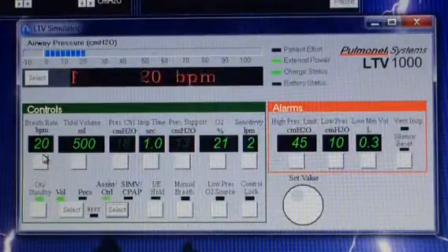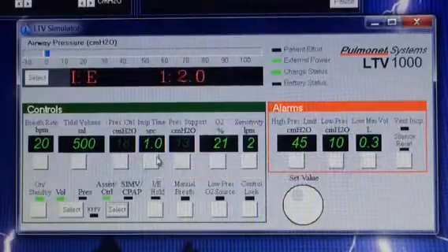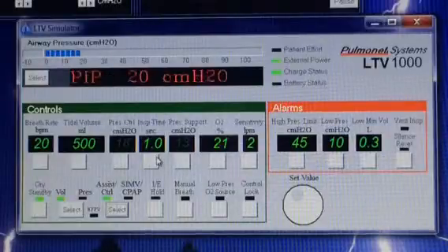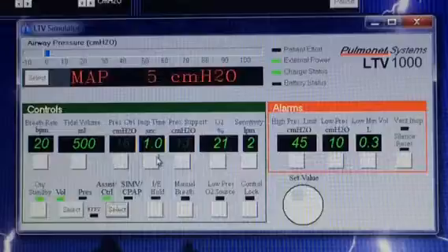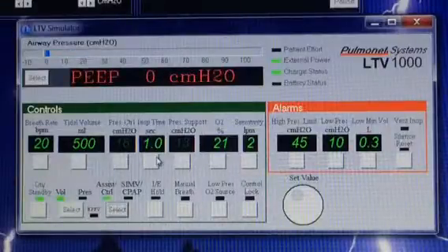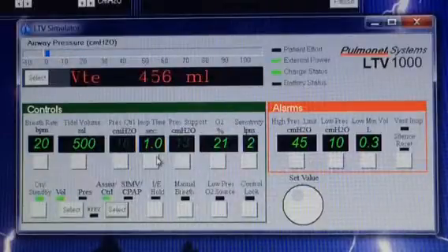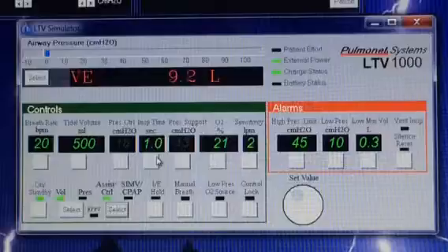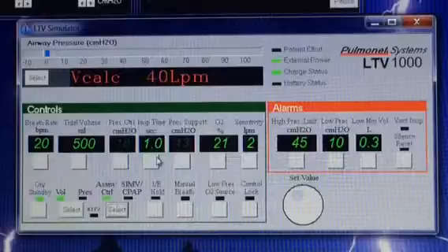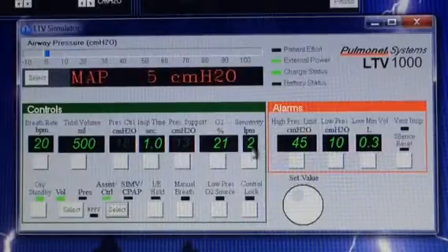So we're going to give 20 breaths per minute, each breath at 500 milliliters, delivered over one second. This patient is either comatose or cannot take a breath on their own. Even with a spinal cord injured patient, usually their diaphragm doesn't work, so they usually cannot take a deep enough breath to stay alive. But they usually have control over their accessory muscles and can take a little breath — just a tiny bit, not enough to keep them alive, but enough for the ventilator to realize it. And that's what we use the sensitivity for.